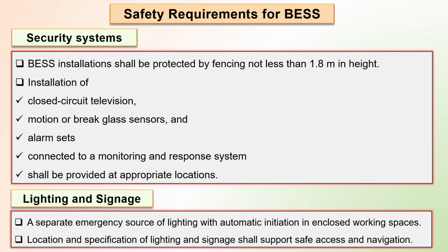Then we have safety requirements for security systems. The BESS installation shall be protected by fencing not less than 1.8 meter in height. There shall be installation of CCTV, motion or break glass sensors, and alarm sets, and they shall be connected to a monitoring and response system and shall be provided at appropriate locations. Then lighting and signage: a separate emergency source of lighting with automatic initiation in enclosed working spaces shall be provided. Location and specification of lighting and signage shall support safe access and navigation.